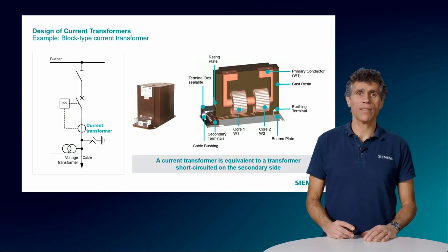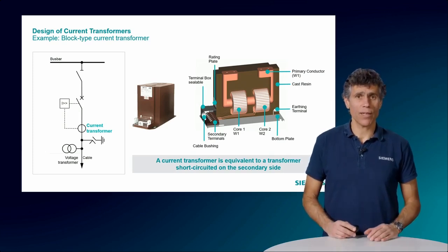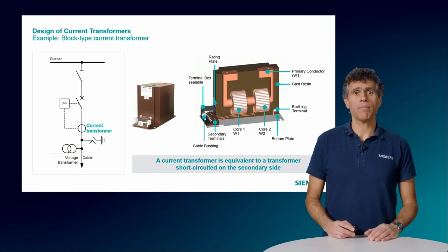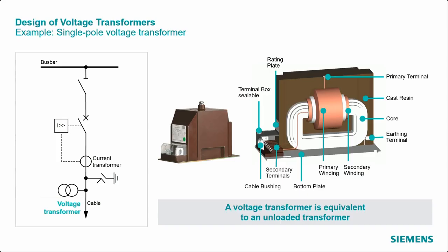Sometimes cores are designed to measure more than one range of primary current, to allow for adjustment or calibration, or to accommodate different primary current levels. This feature enables one current transformer to be used for multiple applications or in situations where the primary current may vary over time. Internally, this might involve selectable taps on the winding, allowing the ratio of primary to secondary current to be adjusted.